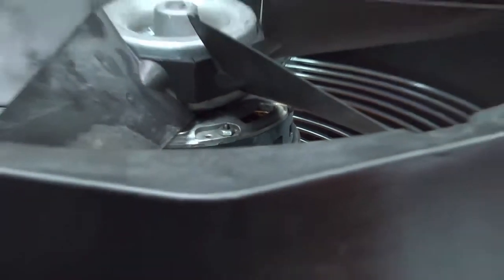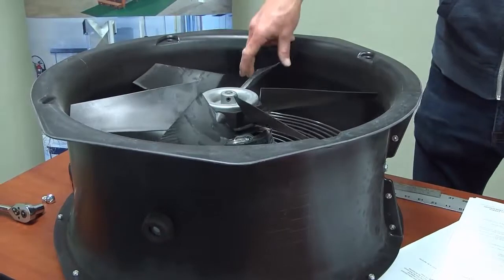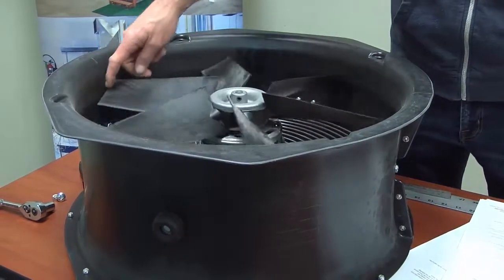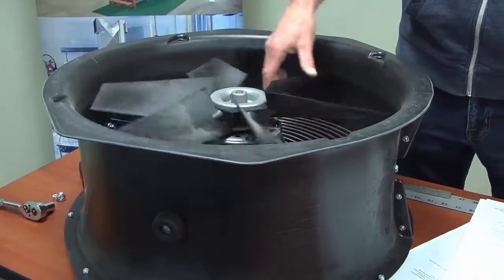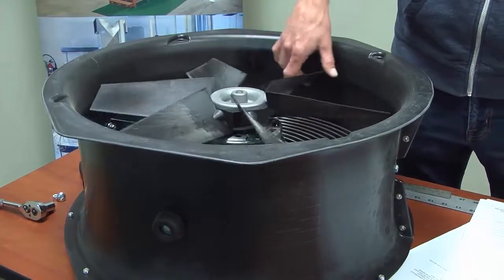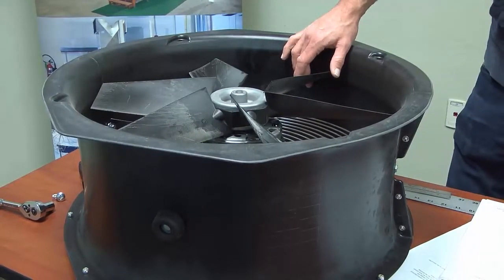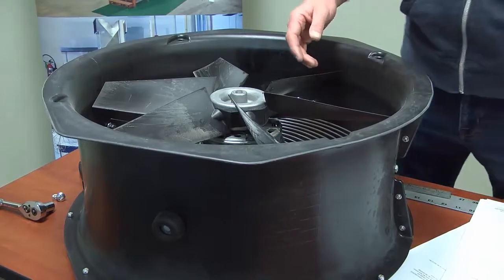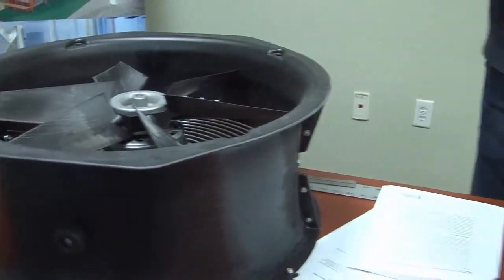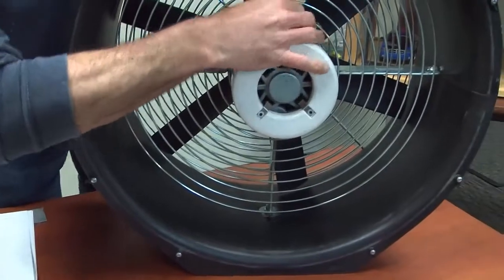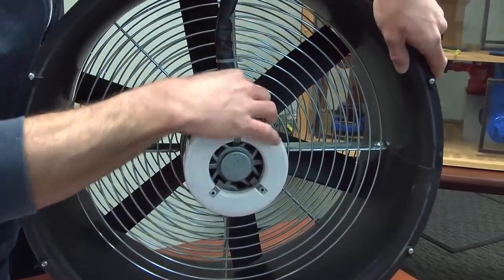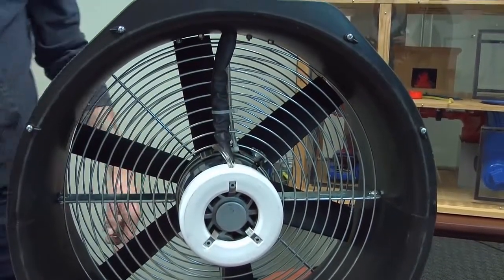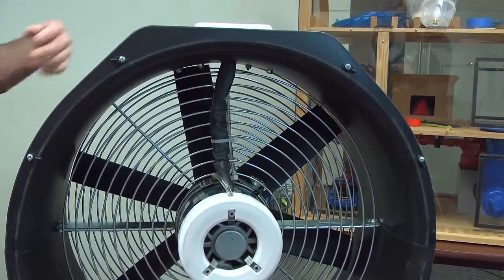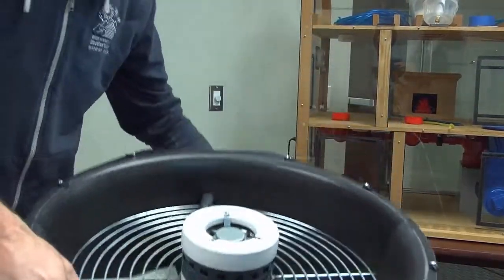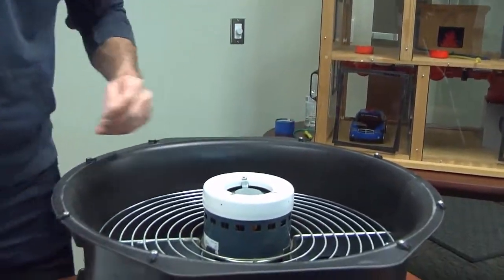And then the other thing is you want to check and make sure your blades are about 1/4 inch off of the housing, so they're not rubbing onto the housing. Another thing to inspect is the electrical wires. On this one, you can see you got your electrical wires running up. You're just checking, making sure nothing's been cut or any kind of issues with wiring.